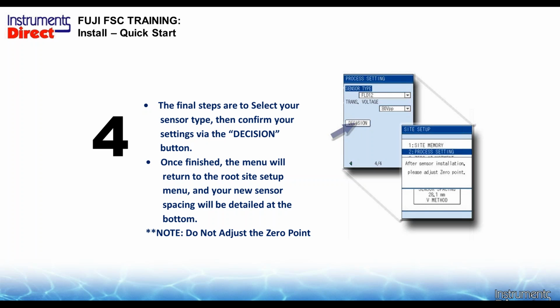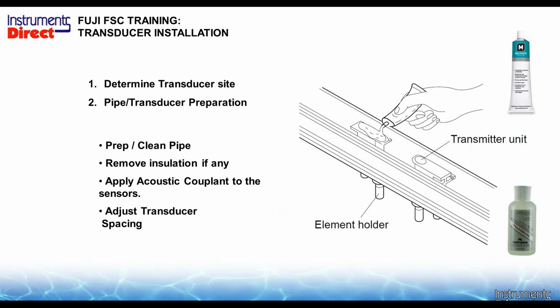If you do zero the flow meter in the field, you may actually insert a fudge factor plus or minus to your flow. So you basically, if you do that, reset the meter. The only time we adjust the zero on a meter is in an application where we're in the 1/10 of a foot per second. So that's an exotic application, so we don't really adjust the zero. And underneath of that, it'll actually show the sensor spacing. This will go away. Sensor spacing will pop up, and that'll be the distance between the 2 transducers.